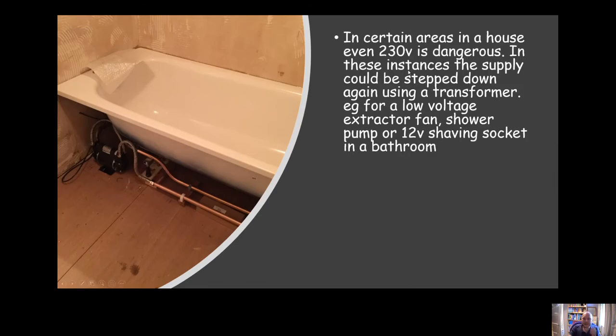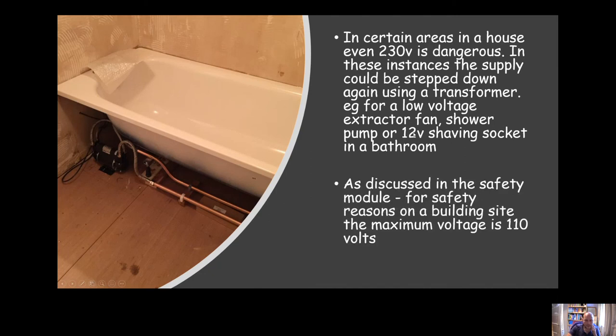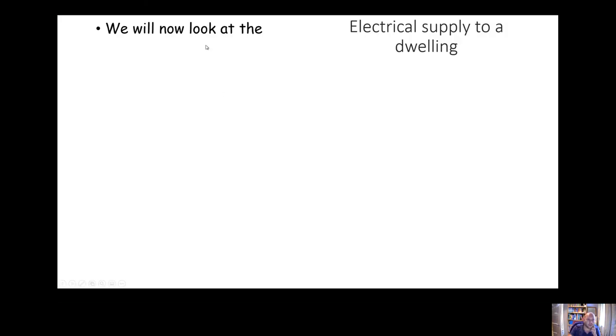In some areas of the house, 230 volts is considered dangerous, so the supply is stepped down using a transformer. For example, an extractor fan right next to a bath should be extra low voltage. Shaving sockets in bathrooms are also ultra low voltage, to minimise the risk of electrocution. On a building site, the maximum voltage is 110 volts.